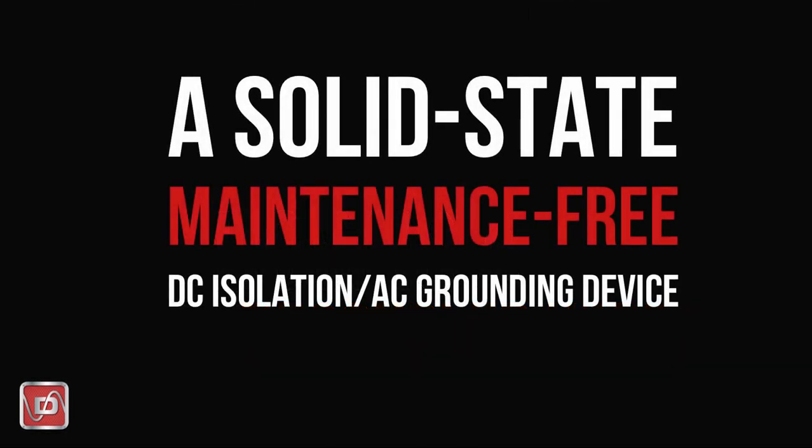What is a decoupler? It's a solid-state, maintenance-free filtering and switching device capable of isolating or blocking DC current while simultaneously conducting AC-induced current and then switching to a protective mode for grounding AC faults and lightning.